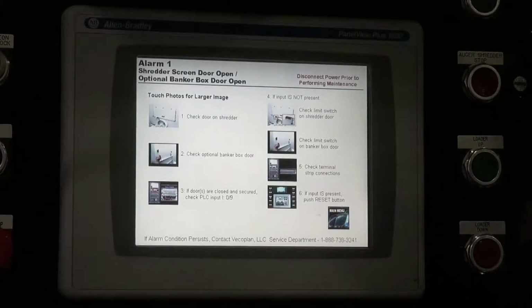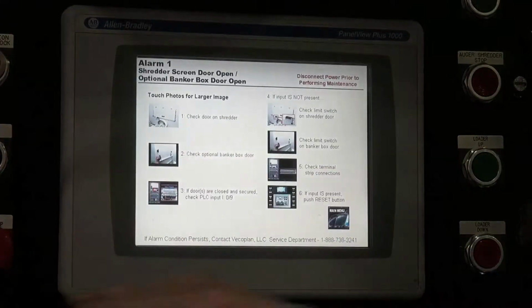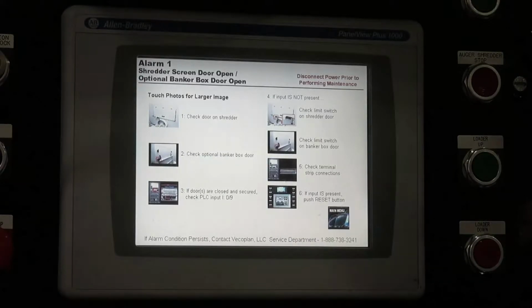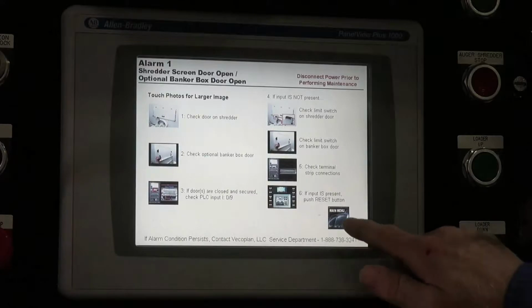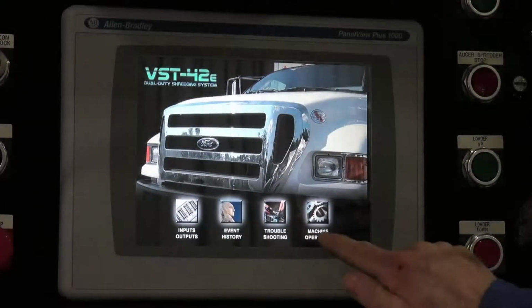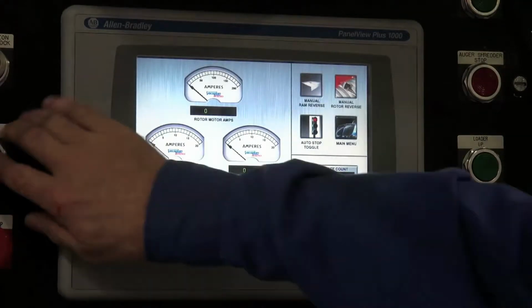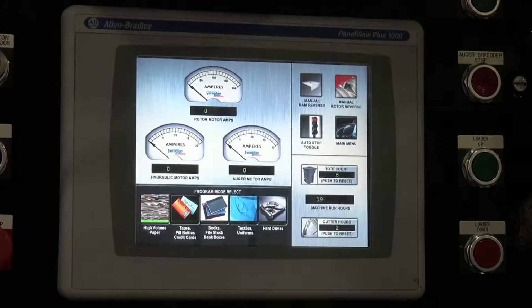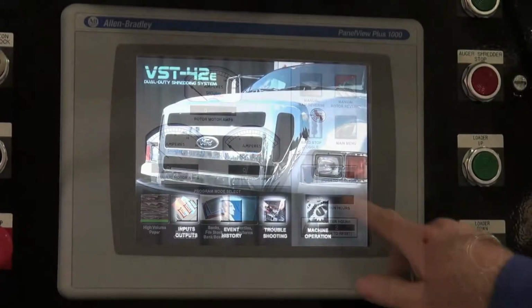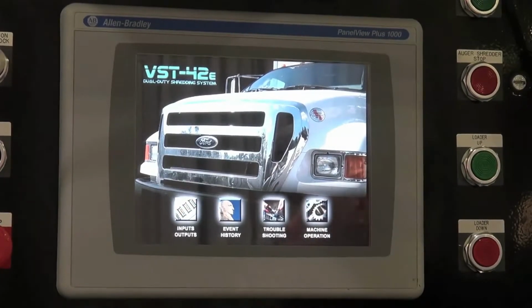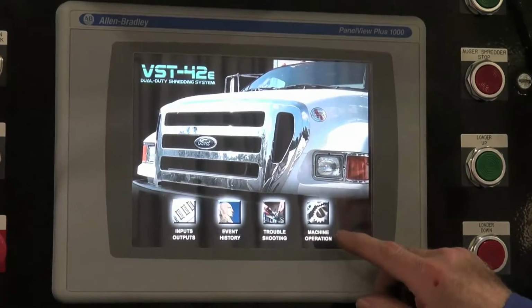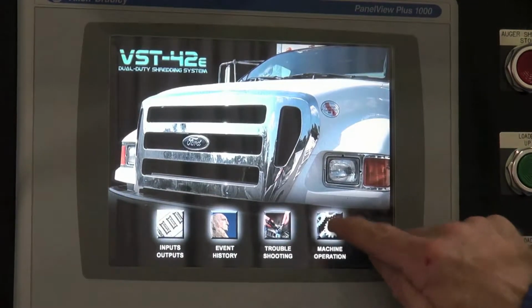This particular fault was caused because the screen door wasn't locked down completely and bounced open off the limit switch we saw earlier in the main menu. Now I can go to my main menu, and go back to my machine operation, push my reset, my fault's clear, my machine's ready. The machine operation screen is a screen that the operator is going to use regularly while he is operating this truck.